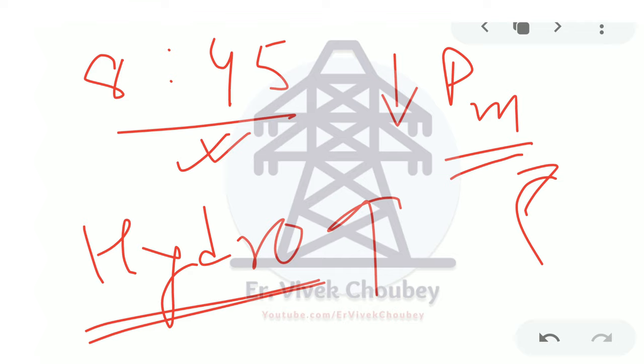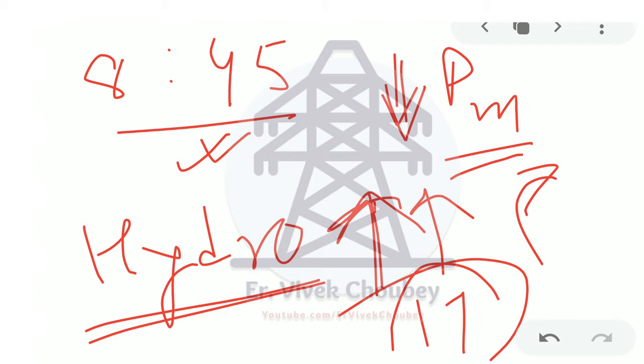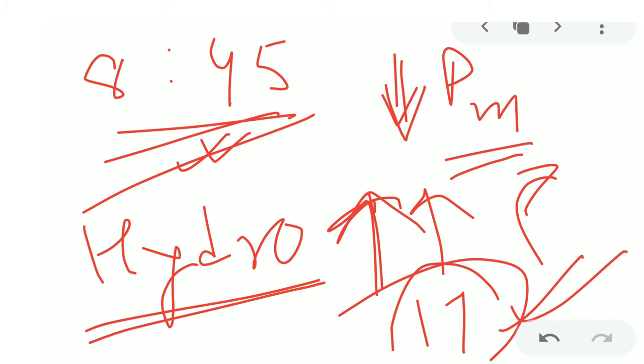Once the whole thing got over, after 9 minutes past 9 p.m., the hydroelectric power generation continued again and kept on increasing. Because as I said, the coal-based thermal power plant cannot go to a new set point so quickly. So the hydroelectric power generation was still working, and in the coal-based thermal power plant the steam input was increased in a gradual manner. It took around 17 minutes for the plant to reach the new set point. So it took 15 minutes for the coal-based thermal power plant to go from high supply to low supply, and then from low supply to high or normal supply, it took another 17 minutes. That's what they said here.